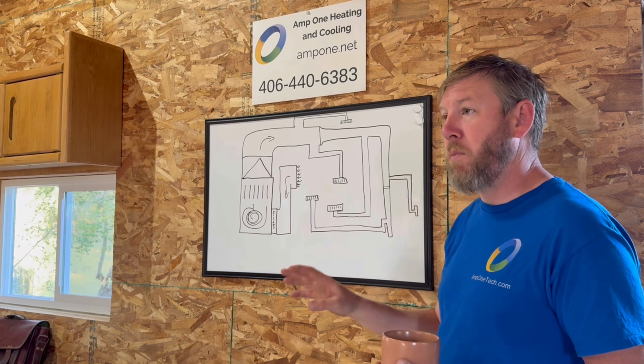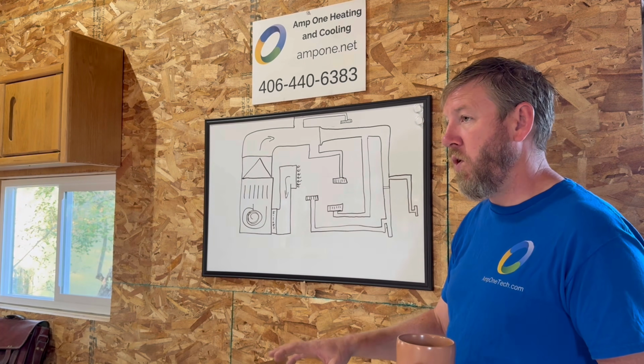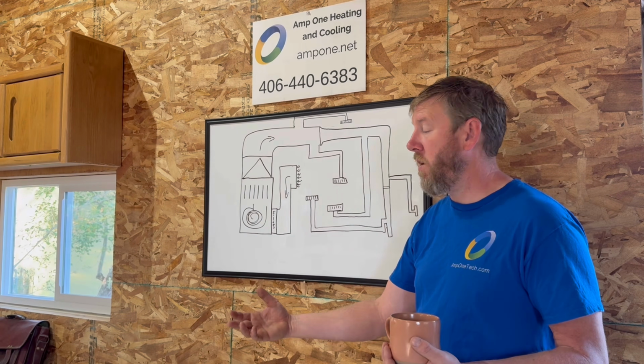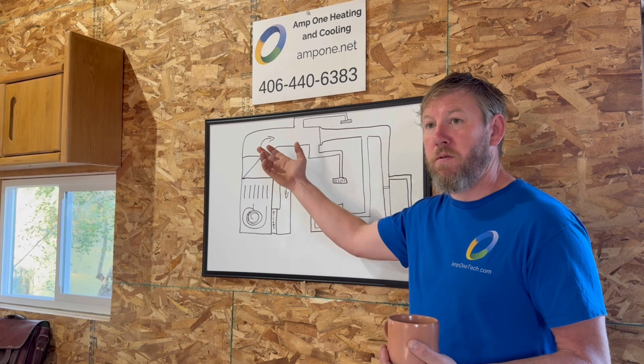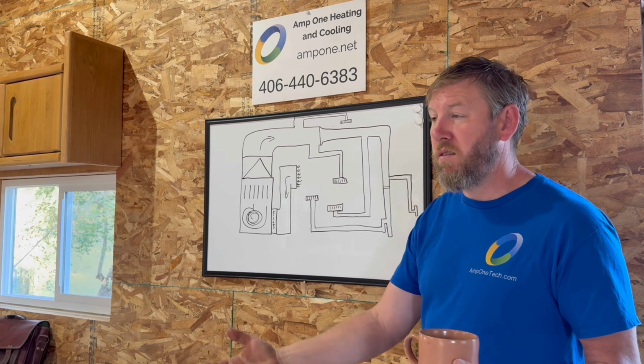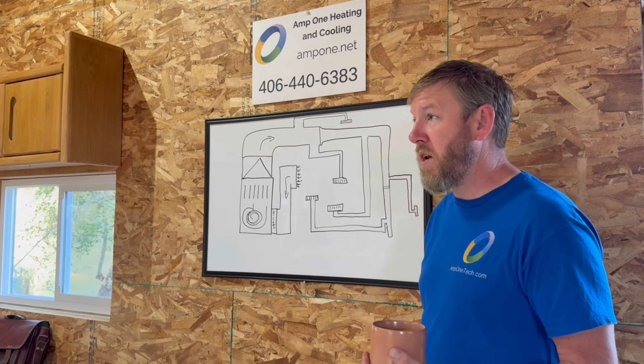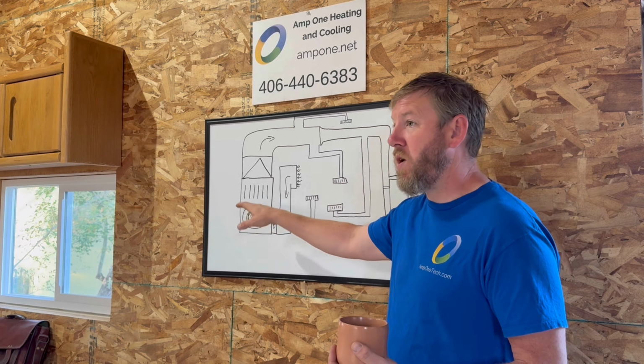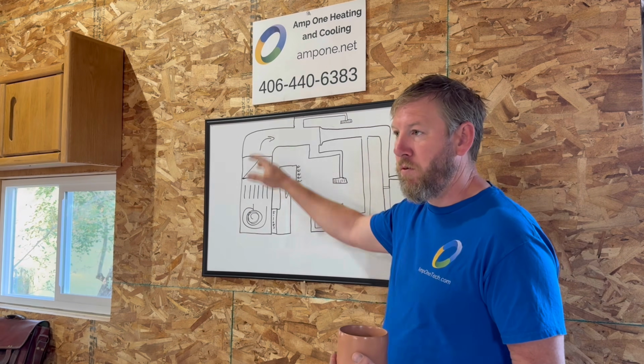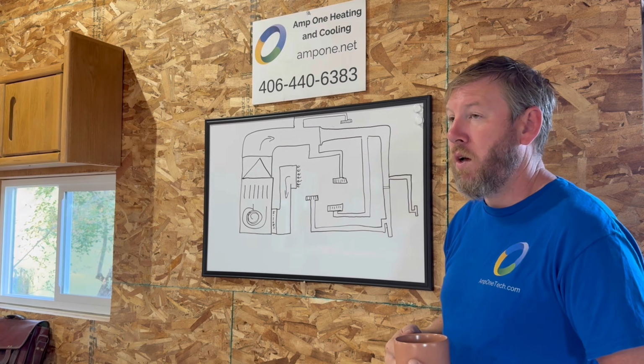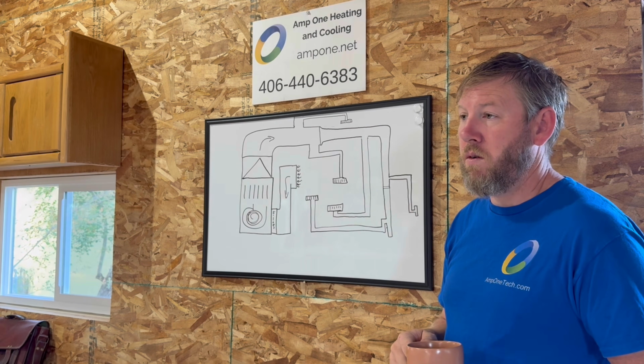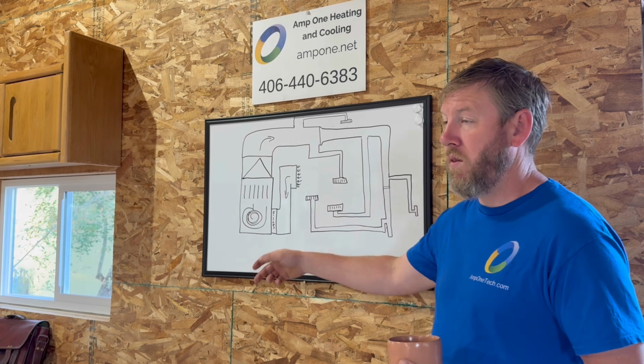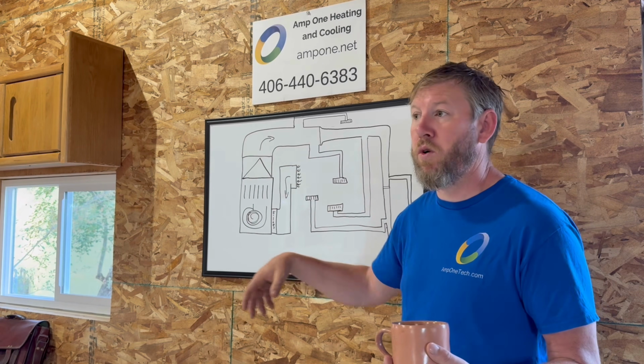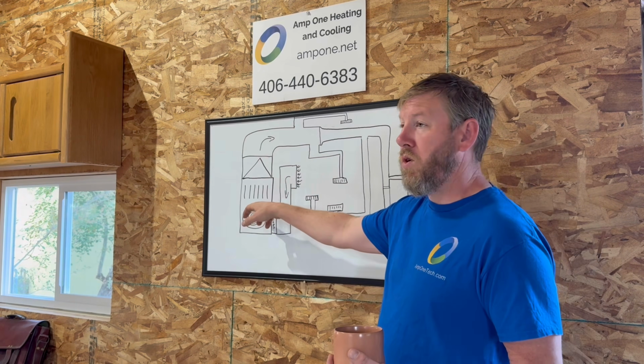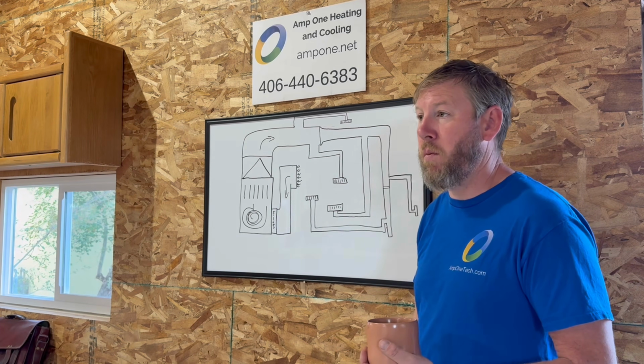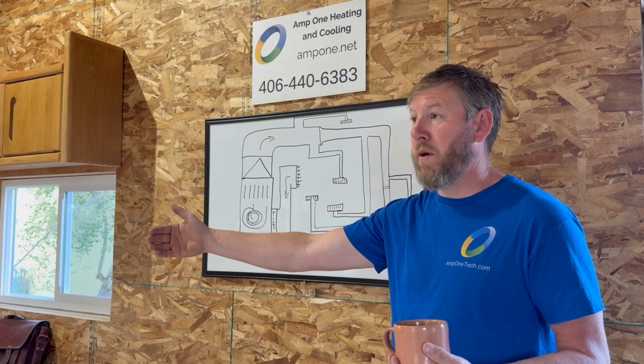Each ton is about 400 CFM. So if it's a 2-ton unit, it's going to pump out 800 CFM, and so on and so forth. If it's a 3-ton furnace, that's just how much airflow it can do. Which one do we have now? A 5-ton. So we need 2,000 CFM. That's why our ductwork is so big, because we're splitting it and doing some zones. We're carrying 2,000 CFM of airflow out to where we need it to be.